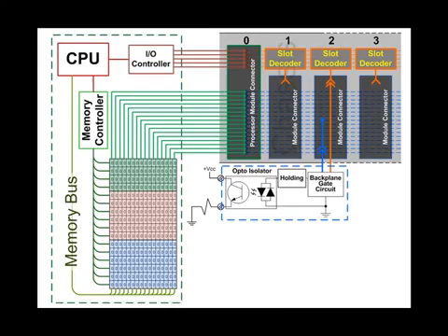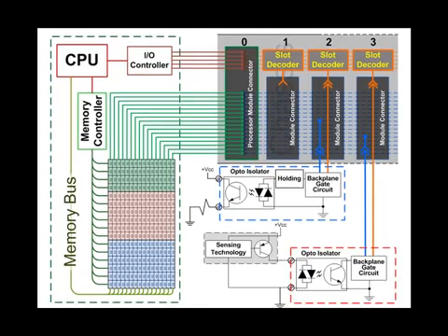First, scanning the backplane by activating input modules one at a time and storing the input images in words of memory associated with each slot that was configured with an input module. Secondly, executing the rungs of logic against the data stored in the data tables, and then scanning the backplane by activating output modules one at a time and transferring the output images from the words in memory associated with each slot that was configured as an output module. Let's examine this sequence in more detail.